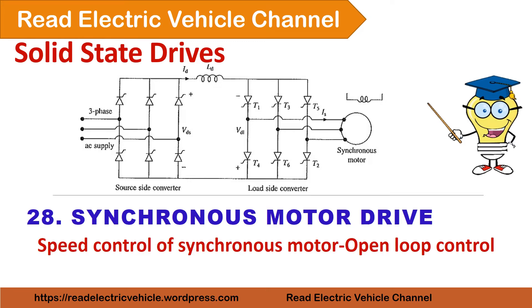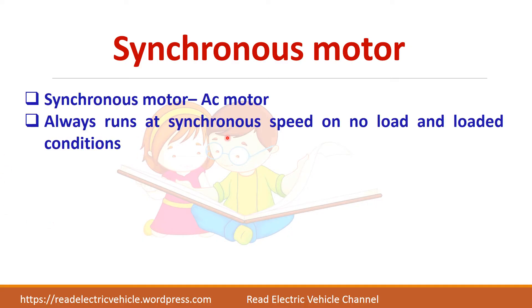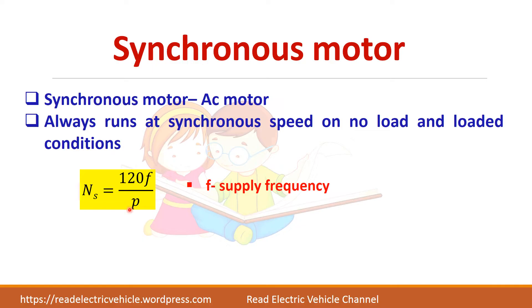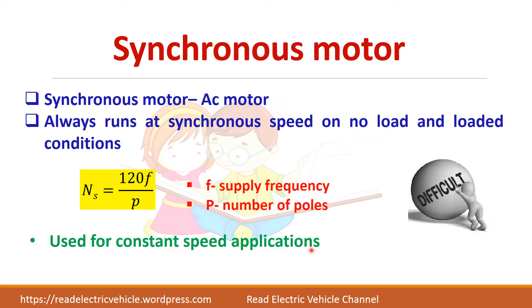In this video, we are going to see about synchronous motor drive. A synchronous motor is an AC motor which will always run at synchronous speed. The synchronous speed is given by 120F by P, where F is the supply frequency and P is the number of poles. Since P is fixed, we have to change the supply frequency to vary speed, which is difficult. So normally synchronous motors were used for constant speed applications, but due to improvements in power electronic converters, nowadays synchronous motors are preferred for variable speed applications also.